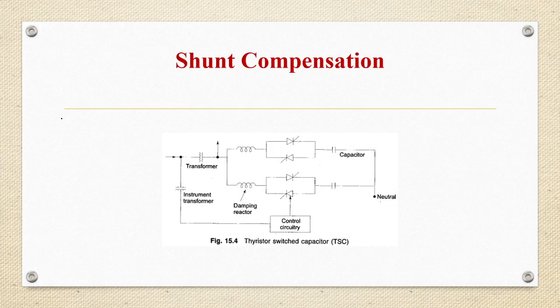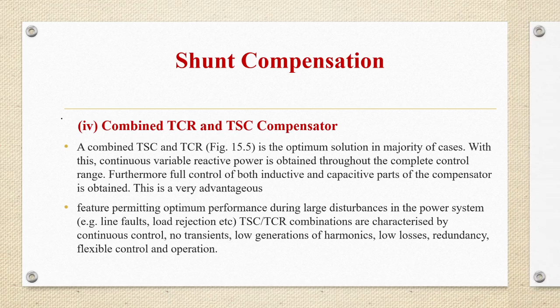So this is a very advantageous feature, permitting optimum performance during large disturbances in the power system, for example line faults, load rejection, etc. So TSC-TCR combinations will be characterized by continuous control, no transients, low generation of harmonics, low losses, redundancy, flexible control and operation.